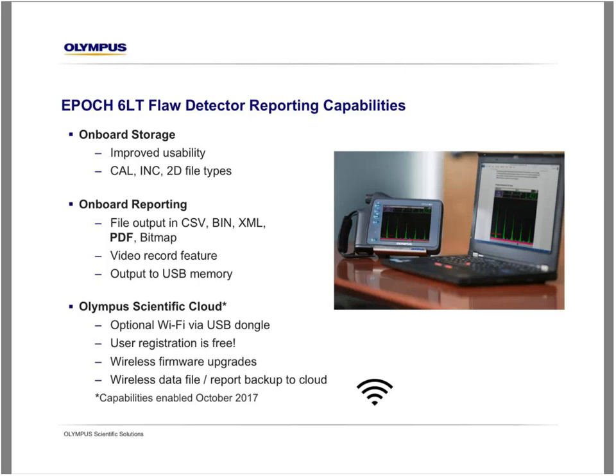We also have a binary file type that allows you to store data on the instrument, and in particular setup files, calibration files, and then swap those files or bring them to other instruments. So if you are managing a fleet of EPOCH 6LT instruments and you have one instrument that has your golden standard calibration files, perhaps for a job that you're working on, you can distribute those files to a variety of different instruments through this binary file type.